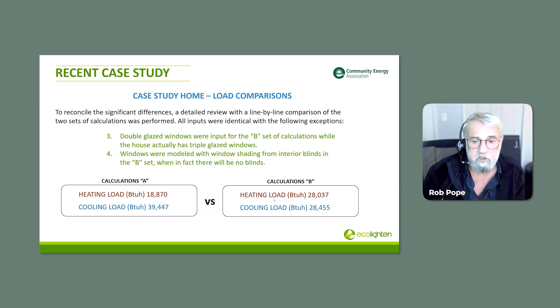Just to encapsulate the issues we discovered: one was the indoor-outdoor design condition, which didn't meet the client's expectations, no resilience, and so on. A large skylight was missed. Double glazed windows were input instead of triple glazed. And windows were modeled with shading from interior blinds when there are no blinds, and even if there were, it would make very little difference anyway.